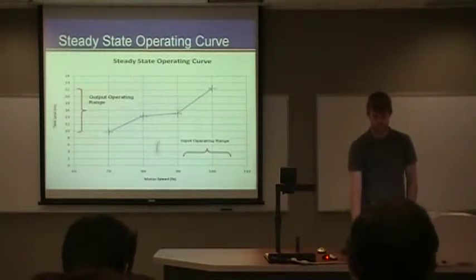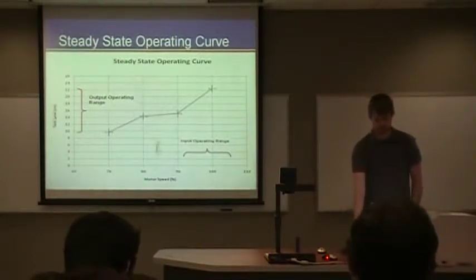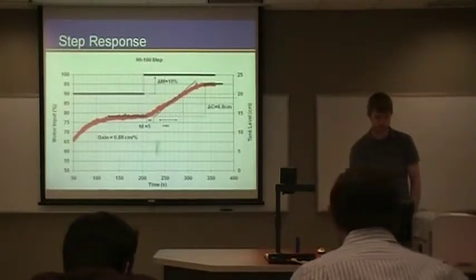Our steady state operating curve, we found that we could operate at between 70 and 100% motor input and get between 9 and 22 centimeters of water head out.